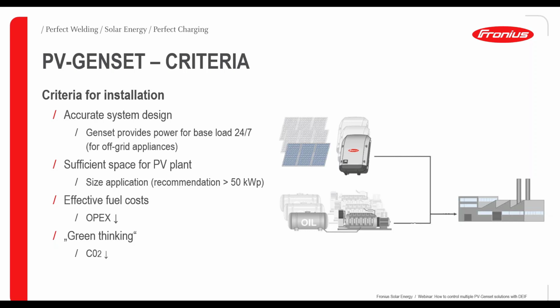First of all, we need to make sure before installing such a PV genset solution that we have an accurate system design. What I mean by that is that we need to make sure that the genset itself, the generator, provides the baseload, the power for the baseload 24/7, if we're talking about the off-grid solution. Reason for that is that the Fronius inverters always need some frequency and voltage to reference to, and of course, therefore we need some reference. It doesn't matter if it's coming from the grid or the genset, but we need to make sure that it is an accurate design.